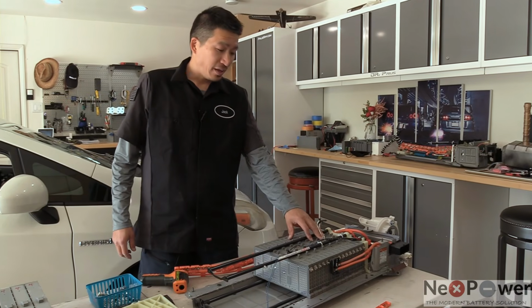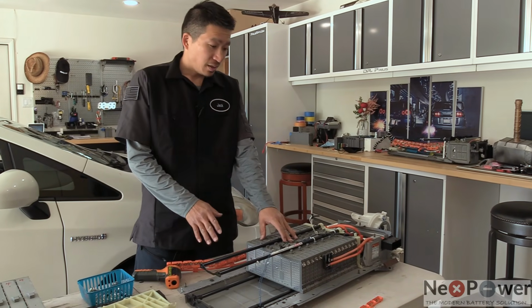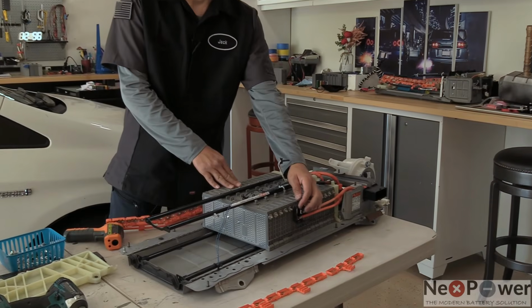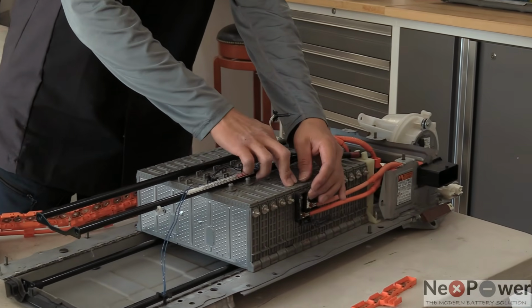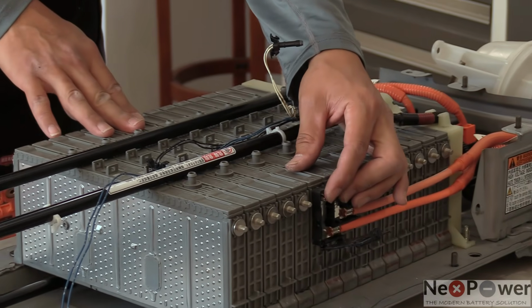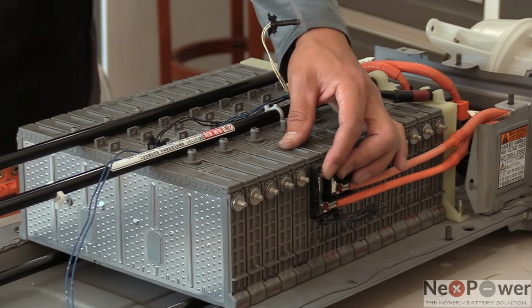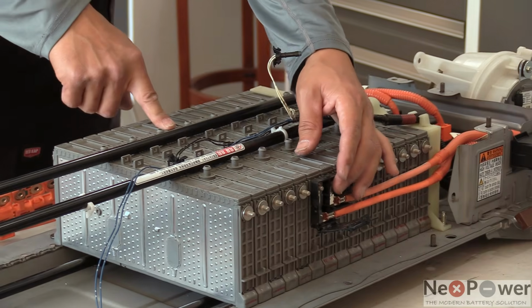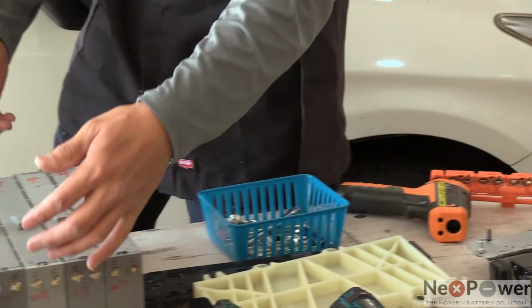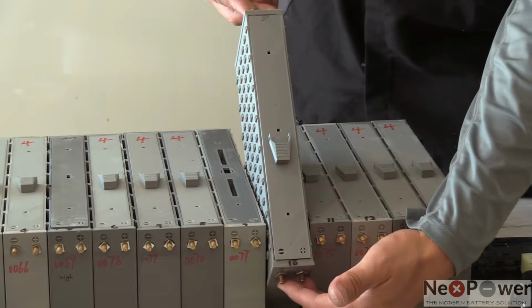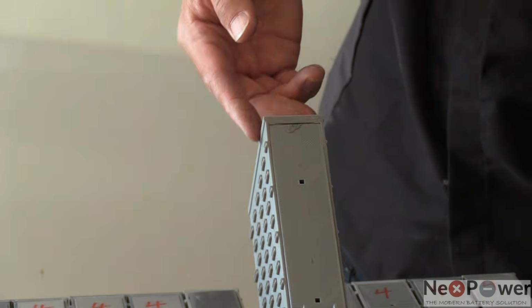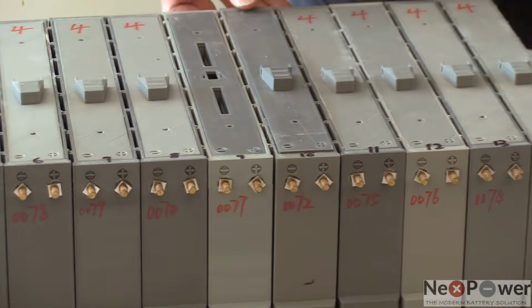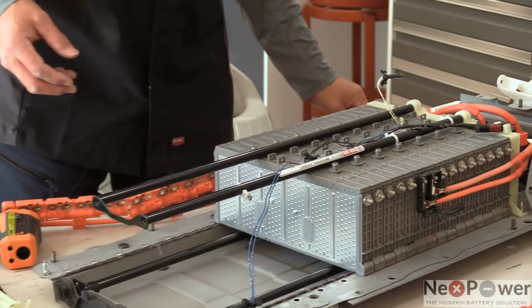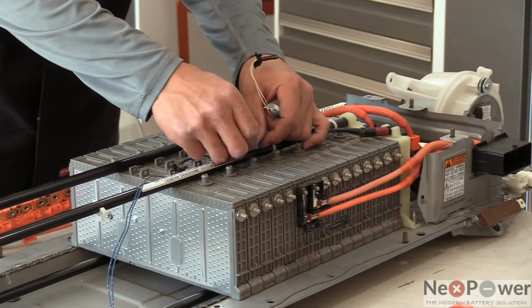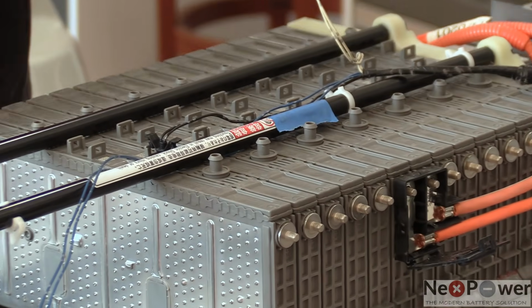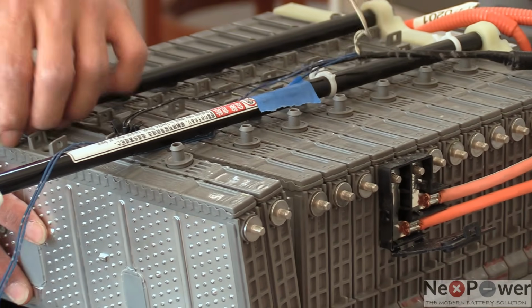Before we remove every single blade from the cradle, pay attention to the service block here. It's connecting to two blades, and when you take it out, you'll have to put the spacer blade back in the same place. The spacer blade is the blade that has a terminal on both sides. To remind you of its place, take a small piece of tape and mark it. Now you can continue to remove all the blades.